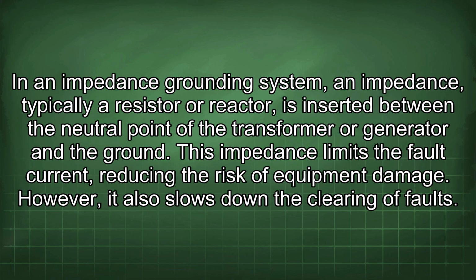In an impedance grounding system, an impedance, typically a resistor or reactor, is inserted between the neutral point of the transformer or generator and the ground. This impedance limits the fault current, reducing the risk of equipment damage. However, it also slows down the clearing of faults.